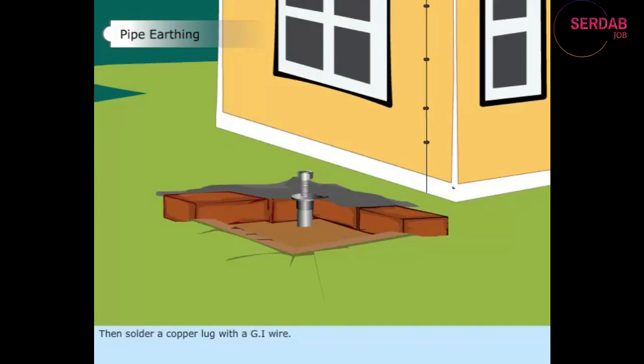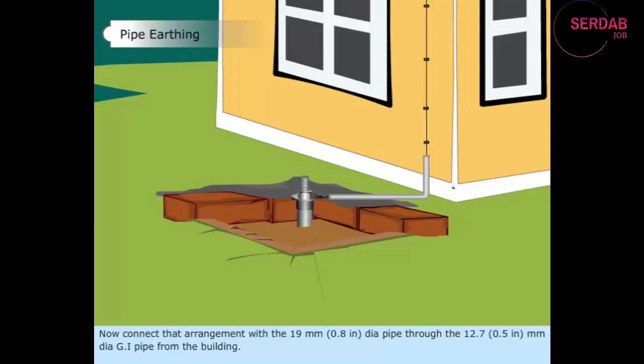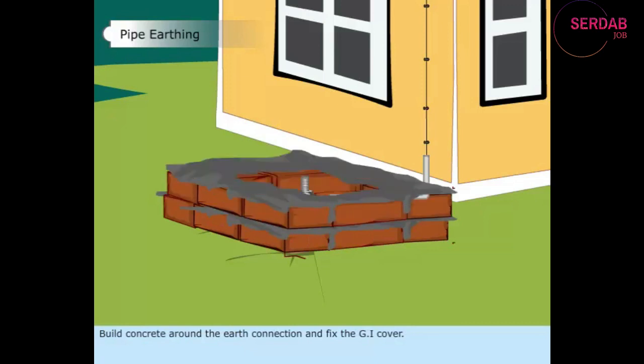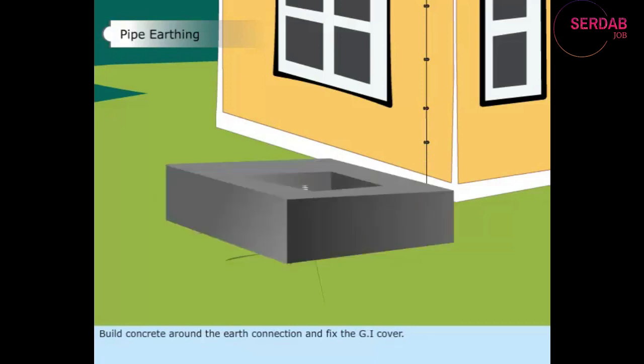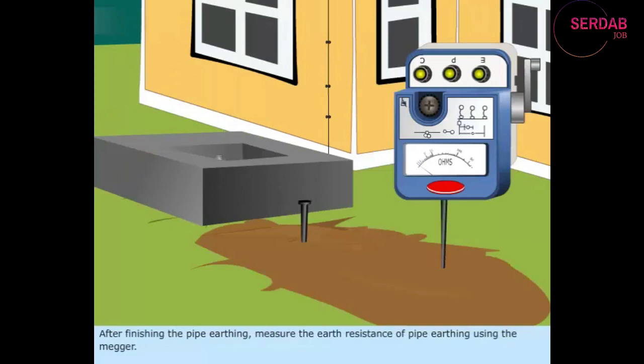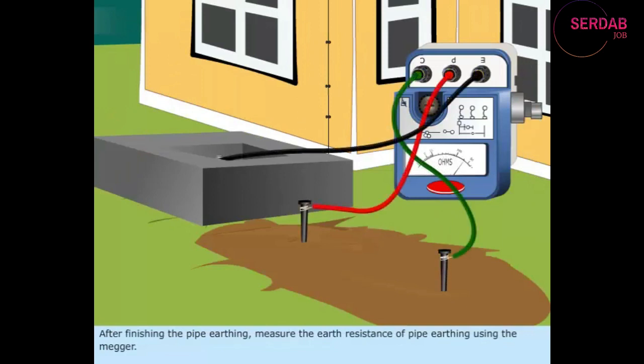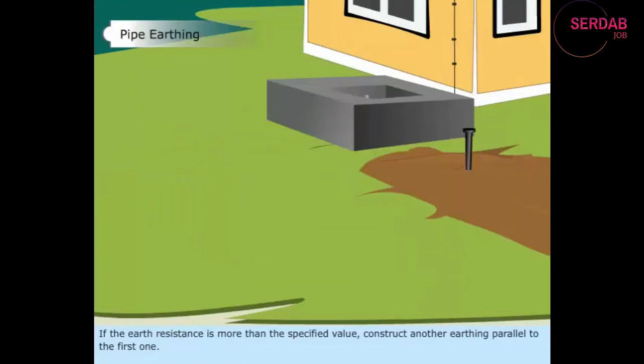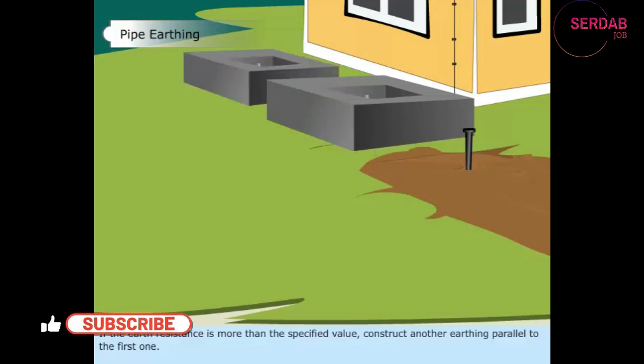Then, solder a copper lug with a GI wire. Now connect that arrangement with the 19 mm, 0.8 inch diameter pipe through the 12.7 mm, 0.5 inch diameter GI pipe from the building. Build concrete around the earth connection and fix the GI cover. After finishing the pipe earthing, measure the earth resistance of pipe earthing using the megger. If the earth resistance is more than the specified value, construct another earthing parallel to the first one. Thus, you have learnt about preparation of a pipe earth wiring.